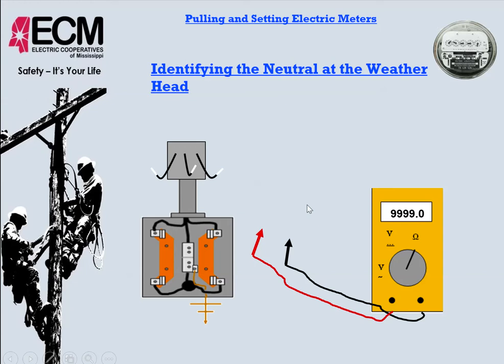And then we'll notice when we do set that multimeter to ohms with our leads separated, it shows an infinity here. Infinity, an infinite amount of resistance. So there's no continuity here if the ends of these meter leads are not touching. So the meter's maxed out. We're measuring resistance, and there's an infinite amount of resistance here, so it would show an overload or 999, just a high number there.